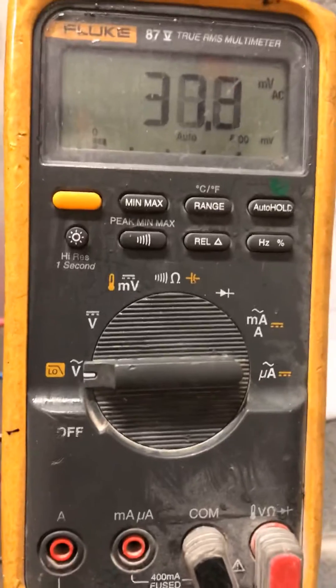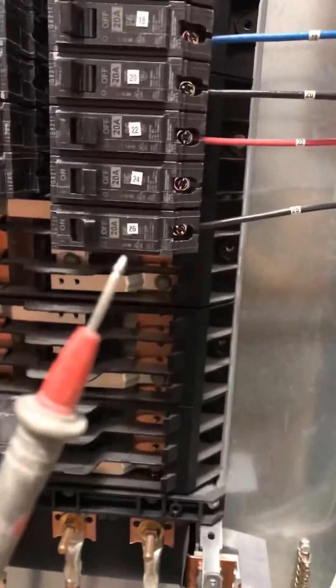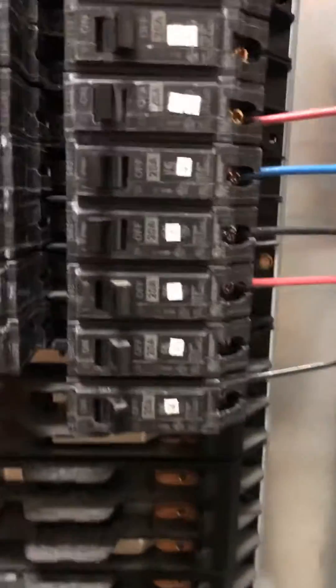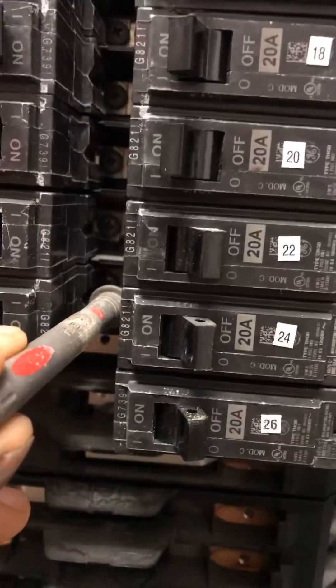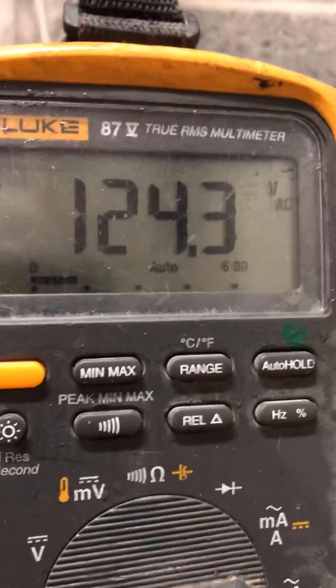You test a breaker by doing this. I have my one lead on the ground. The other lead, I am going to take and place it where it is getting fed at. I'm going to verify that I have power, which I do.